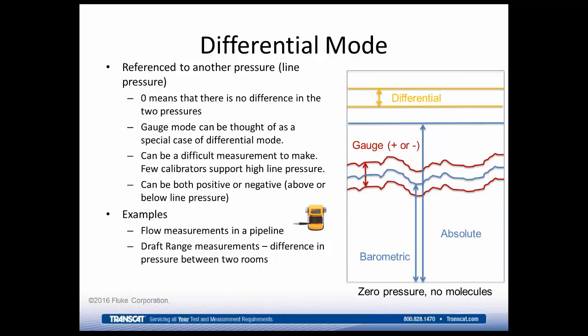The third main reference mode is what we call differential mode. And that's where your pressure is referenced to another pressure. In many ways, you can think of all pressures as being differential mode, with gauge and absolute being special types of that, where the other pressure that you're referenced to is either atmosphere, in the case of gauge mode, or a perfect vacuum in the case of absolute mode. Differential mode is just saying that it's referenced to another pressure.